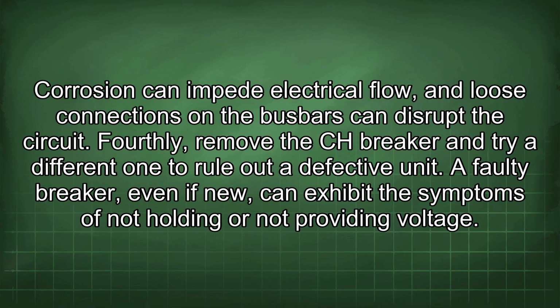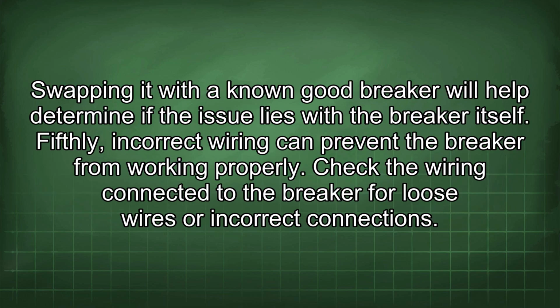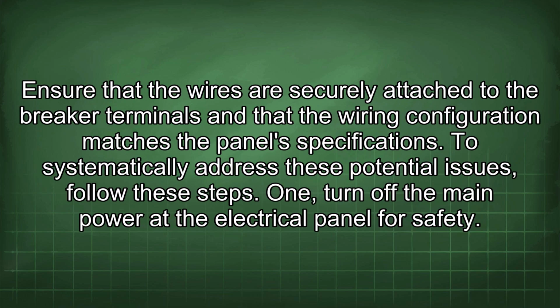Fourthly, remove the CH breaker and try a different one to rule out a defective unit. A faulty breaker, even if new, can exhibit the symptoms of not holding or not providing voltage. Swapping it with a known good breaker will help determine if the issue lies with the breaker itself. Fifthly, incorrect wiring can prevent the breaker from working properly. Check the wiring connected to the breaker for loose wires or incorrect connections. Ensure that the wires are securely attached to the breaker terminals and that the wiring configuration matches the panel's specifications.